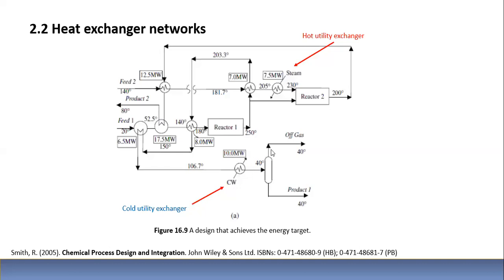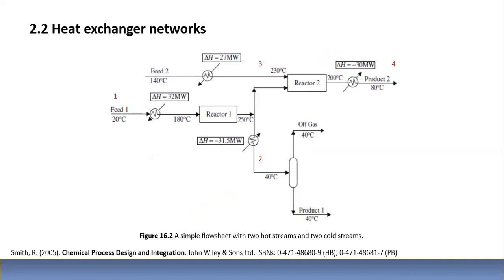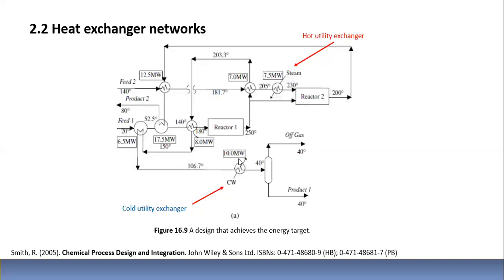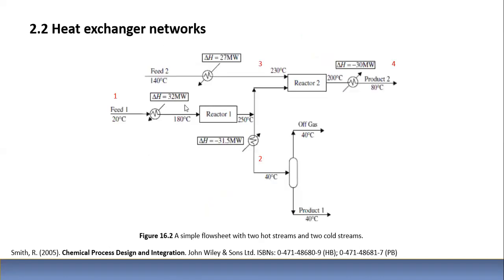And now you only need to absorb 10 megawatts instead of 61.5 megawatts between the 2 of them. If you divide 10 by 61.5, now you're only requiring 16% of what you were requiring in this non-efficient process. But you also see that there is an additional amount of exchangers required for this process heat recovery between hot streams and cold streams. You have 1, 2, 3, 4, 5, 6 additional exchangers to the exchanger using the hot utility and the cold utility. So in total, you need 8 exchangers instead of 4.